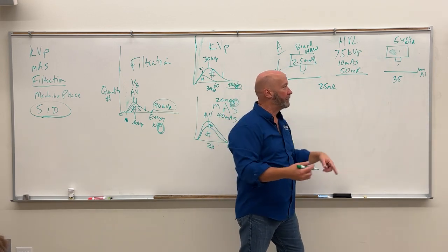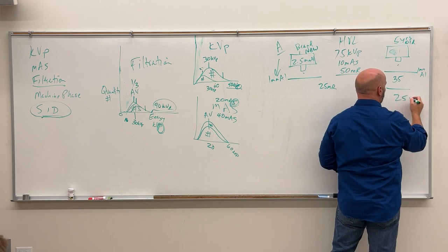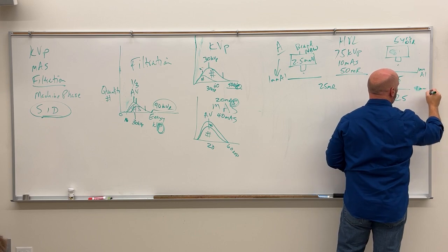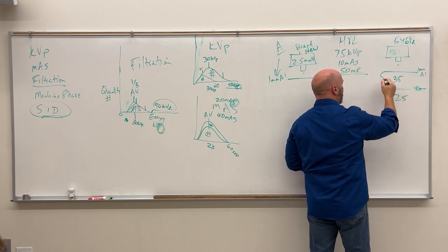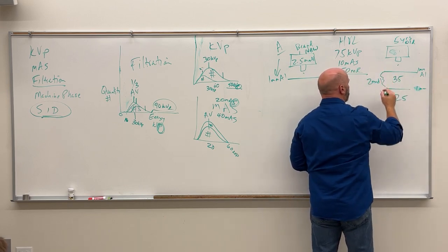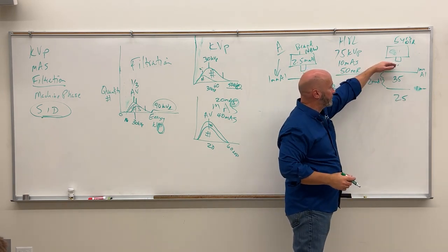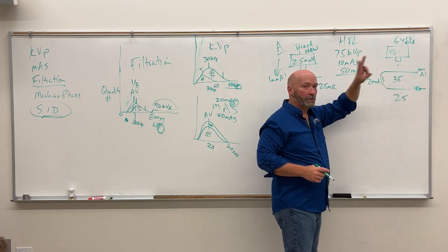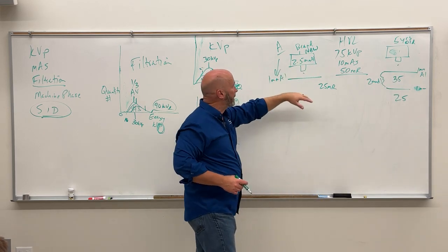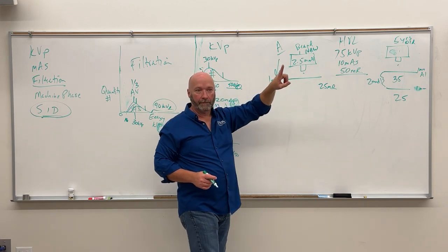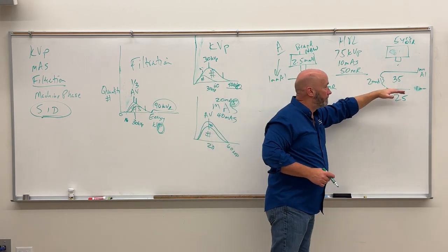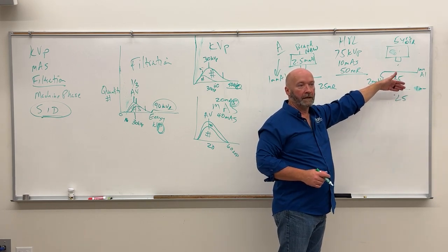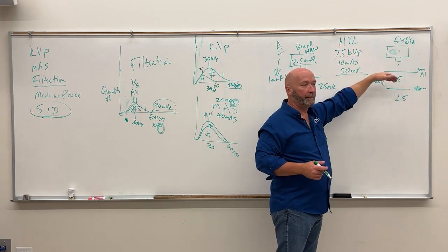That one, right? So if we add a second one, and it drops it to 25, we've got now 1 millimeter and another millimeter of aluminum, and it takes 2 millimeters of aluminum to get to half of its original intensity. We can say the half value layer of beam B is 2 millimeters of aluminum. Half value layer of beam A is 1 millimeter of aluminum, right? So higher quality X-ray beam. Okay, so it's a better measure. They're both 75 KVP, but this one penetrates more.